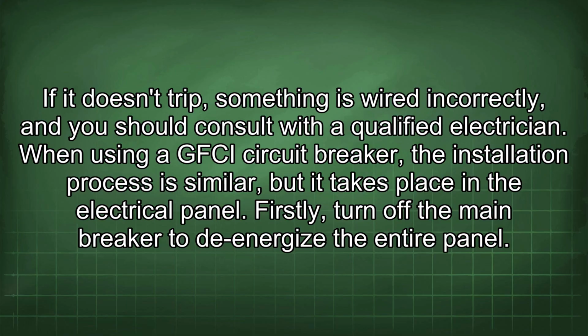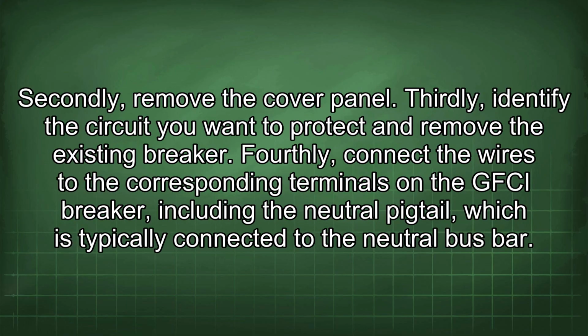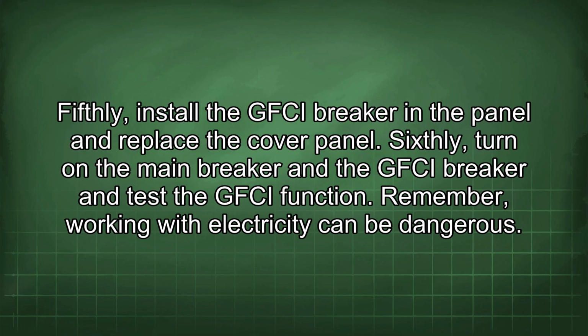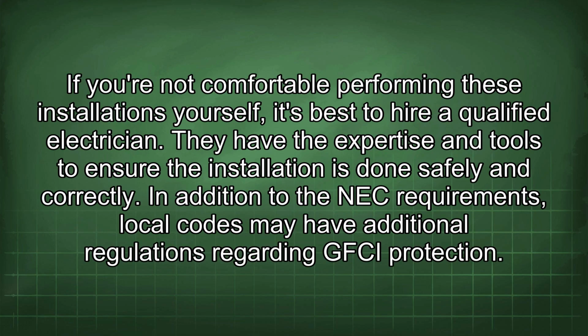When using a GFCI circuit breaker, the installation process is similar, but it takes place in the electrical panel. Firstly, turn off the main breaker to de-energize the entire panel. Secondly, remove the cover panel. Thirdly, identify the circuit you want to protect and remove the existing breaker. Fourthly, connect the wires to the corresponding terminals on the GFCI breaker, including the neutral pigtail, which is typically connected to the neutral bus bar. Fifthly, install the GFCI breaker in the panel and replace the cover panel. Sixthly, turn on the main breaker and the GFCI breaker and test the GFCI function. Remember, working with electricity can be dangerous. If you're not comfortable performing these installations yourself, it's best to hire a qualified electrician. They have the expertise and tools to ensure the installation is done safely and correctly.